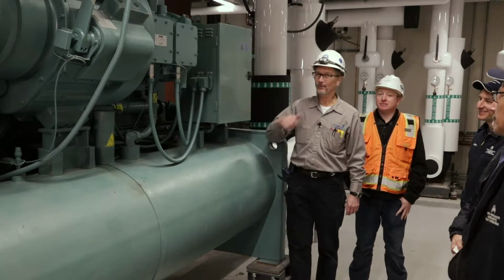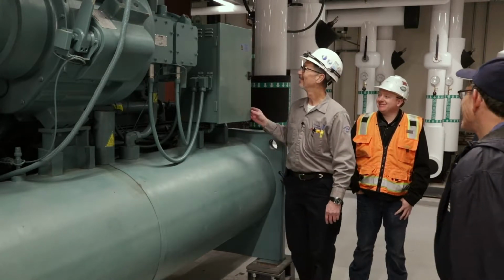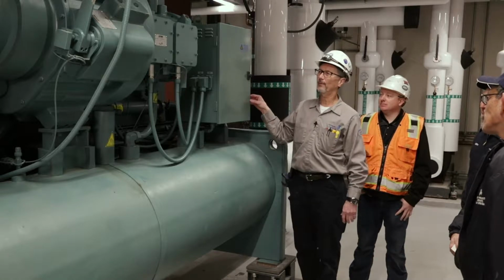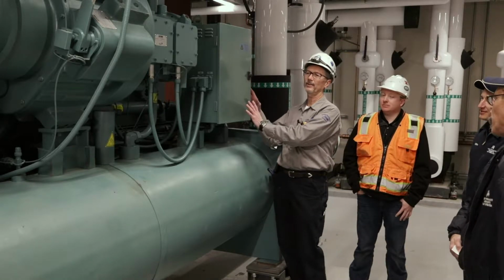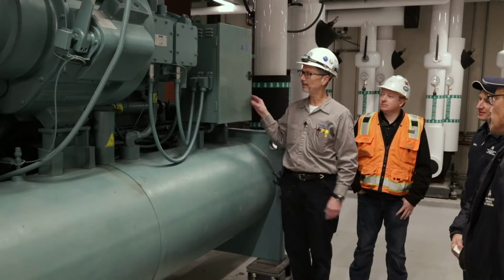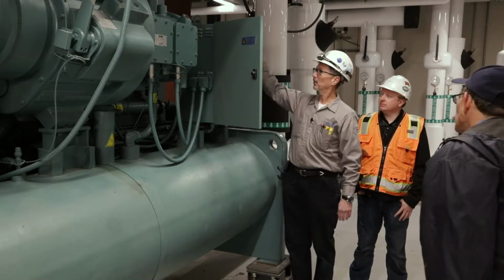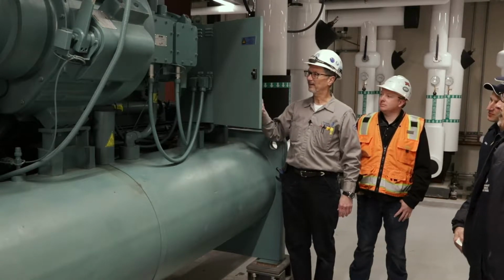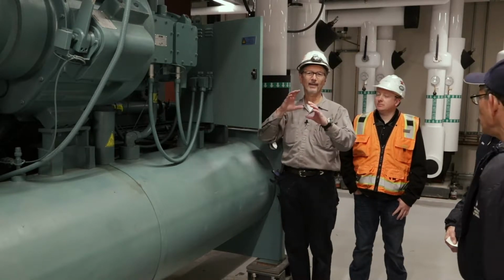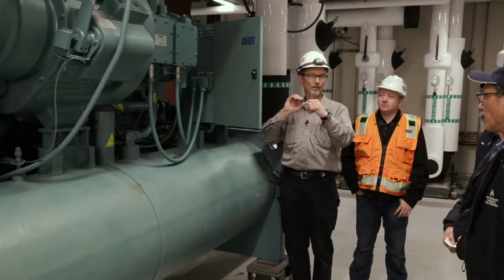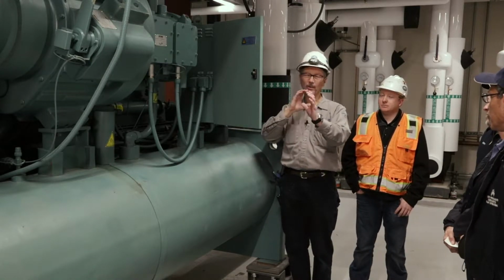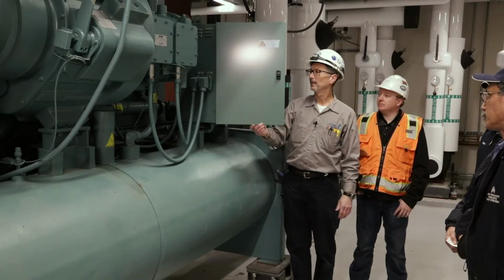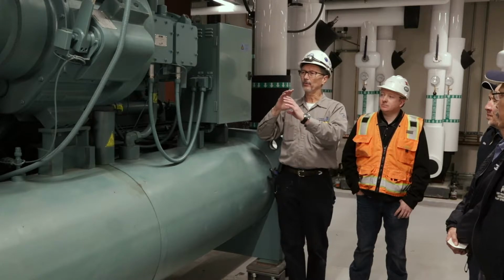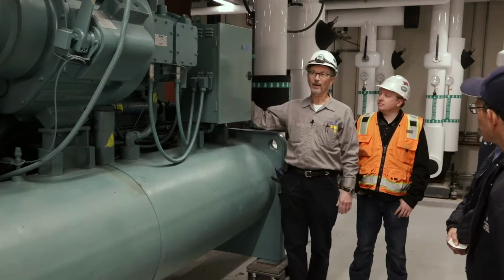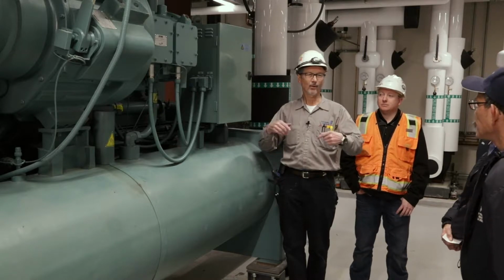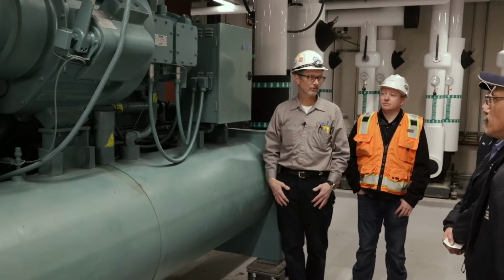Okay, now we're going to talk about the compressor and the motor today. This is the control panel for the motor, or the magnetic bearing. So this panel only deals with the magnetic bearing on its own. A signal comes from the main controller to activate this, and then this basically does its own thing, maintaining a position of the shaft of the rotor all the time. That's all it does is maintain that. And then after it levitates the rotor, the frequency drive then begins to spin the rotor at whatever speed we're looking for to meet load on the chiller.